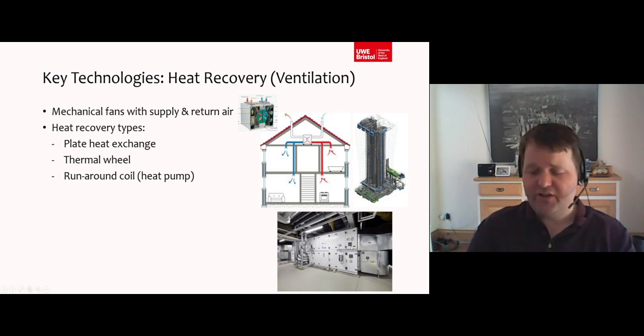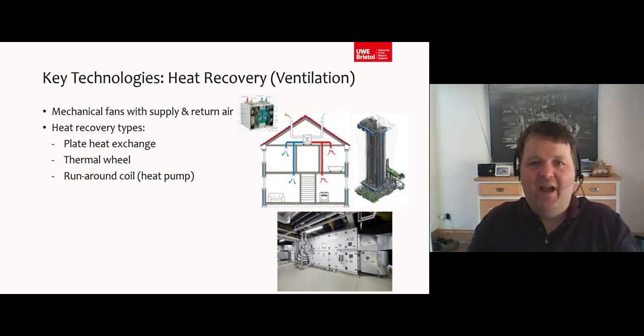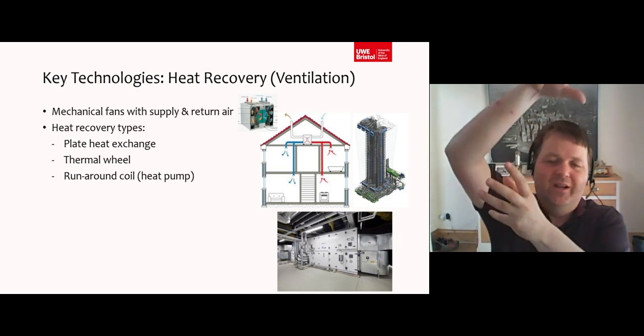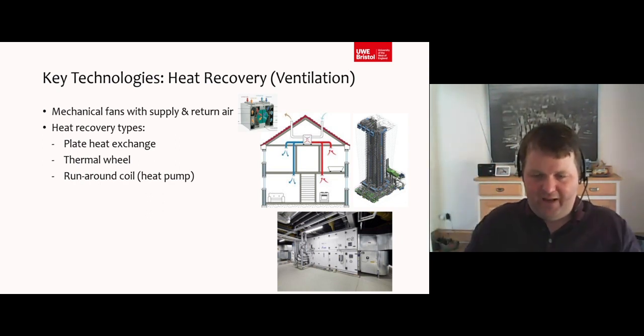In commercial scenarios, you also get an option called a thermal wheel. A thermal wheel is something that slowly moves from one airstream into the other. It's made of a heavy thermal mass, and it picks up heat in your exhaust space. And then as it turns into the fresh air, it drops that heat back again into the fresh air. These two systems are about equally as efficient as one another at recovering that heat.